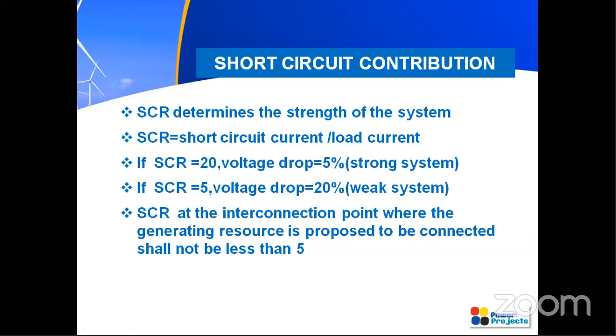Coming to the short circuit current, if you have very little current, an SCR of 5 is a weak system, so the stability will be very low. An SCR of 20 is a strong system, so the stability will be more. So this is related one way or the other to the stability of the system also. We always prefer a system with higher SCR values. That's why the grid code requirements stress that the SCR at the interconnection point, where you are integrating your wind farms with the grid, should not be less than 5.